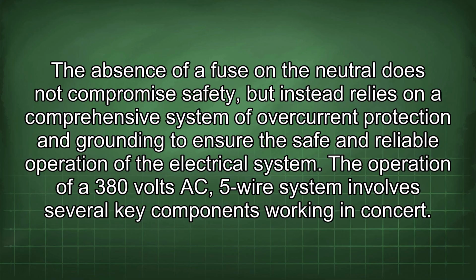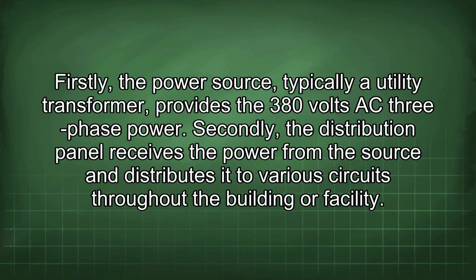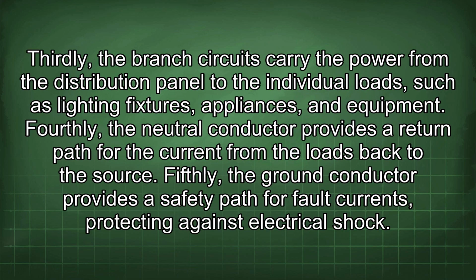The operation of a 380 volts AC 5-wire system involves several key components working in concert. Firstly, the power source, typically a utility transformer, provides the 380 volts AC 3-phase power. Secondly, the distribution panel receives the power from the source and distributes it to various circuits throughout the building or facility. Thirdly, the branch circuits carry the power from the distribution panel to the individual loads such as lighting fixtures, appliances, and equipment. Fourthly, the neutral conductor provides a return path for the current from the loads back to the source. Fifthly, the ground conductor provides a safety path for fault currents, protecting against electrical shock.